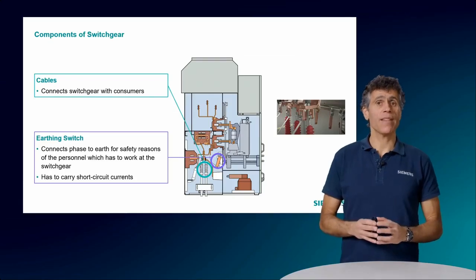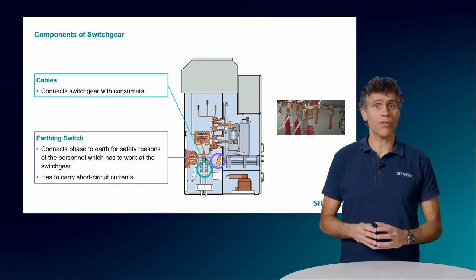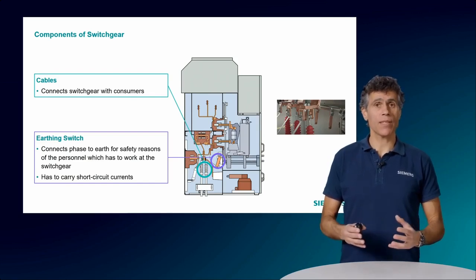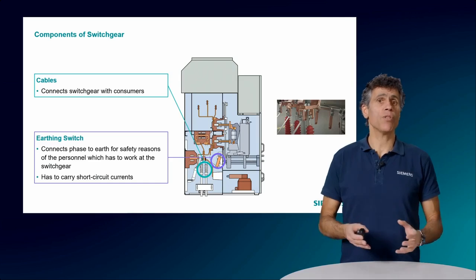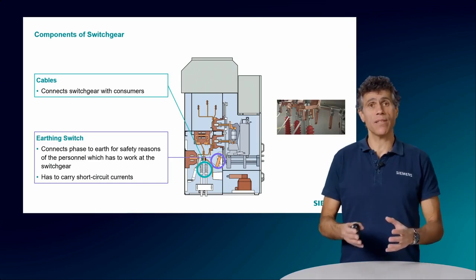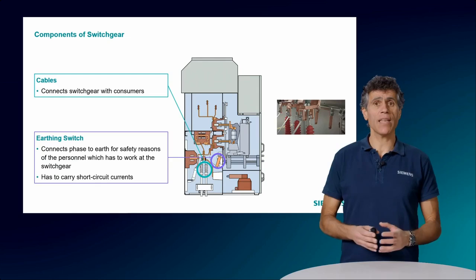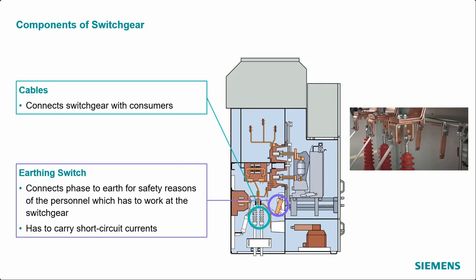Of course, there are mechanical and electrical interlocks, some of them even mandatory, to prevent all these failures. For example, the earthing switch cannot be switched on while the breaker is inserted. But nevertheless, the earthing switch is usually built in a way that it can withstand that amount of electrical, thermal and mechanical stress in case all interlocks go wrong. And here you can see how impressive such duties can be.